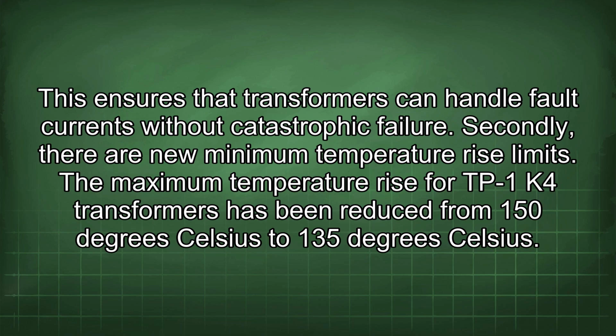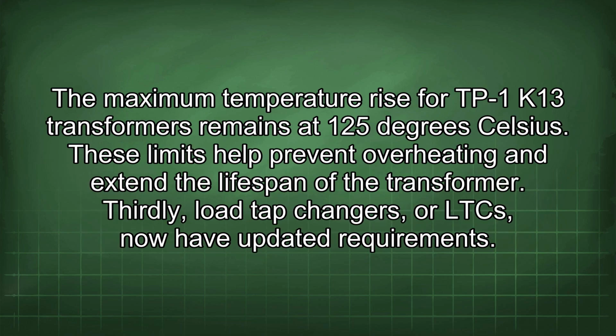Secondly, there are new maximum temperature rise limits. The maximum temperature rise for TP-1 K4 transformers is being reduced from 150 degrees Celsius to 135 degrees Celsius. The maximum temperature rise for TP-1 K13 transformers remains at 125 degrees Celsius. These limits help prevent overheating and extend the lifespan of the transformer.